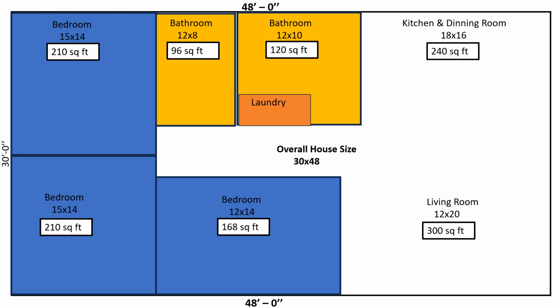So finding out what is my heat load, you need to know what your heat load is for a couple of reasons. When you're setting a furnace, let's say this one is going to be a split system, and we're going to use one of our 3-ton air handlers and a 3-ton heat pump condenser on the outside just for this particular podcast. And we can go over different ways of doing it in another podcast.